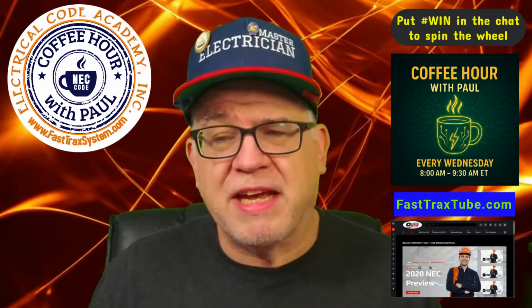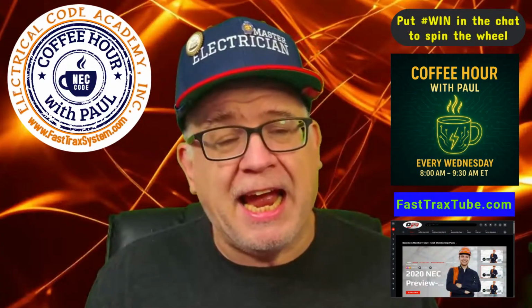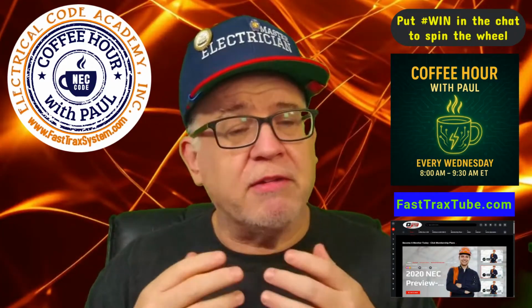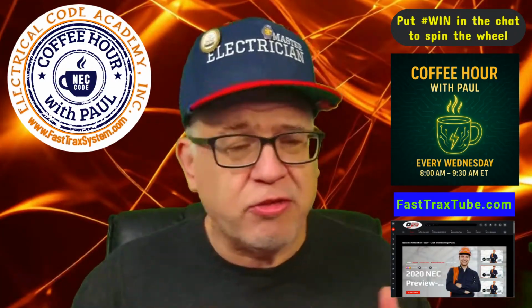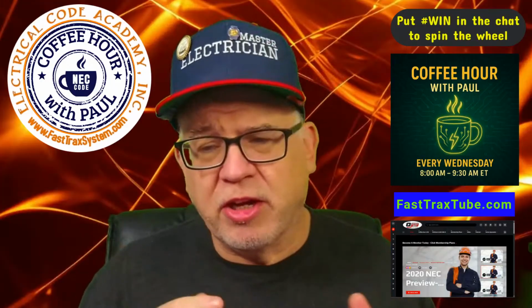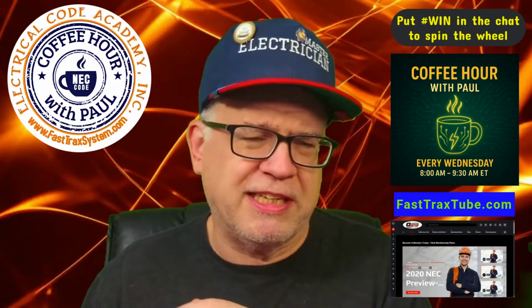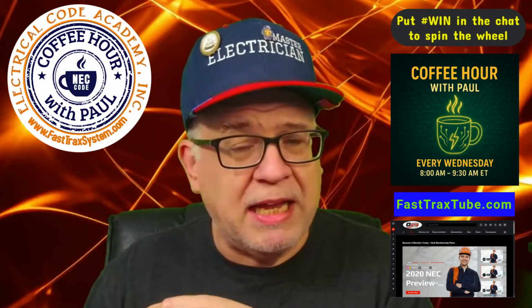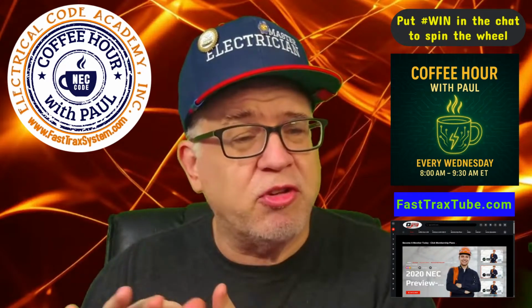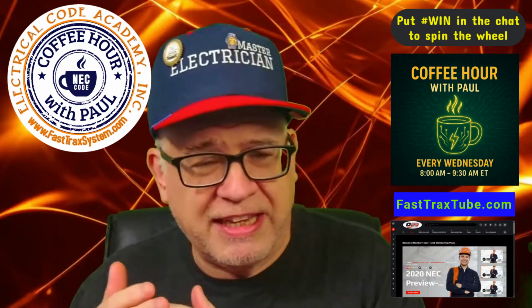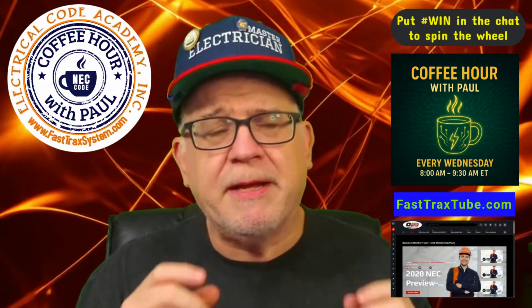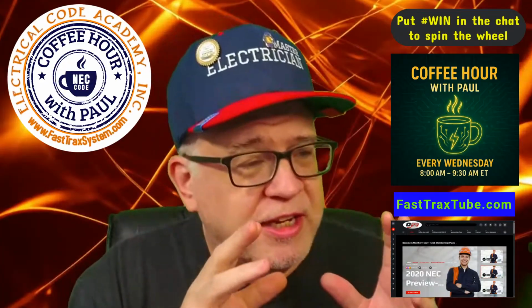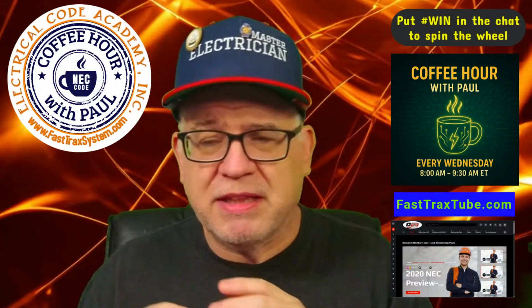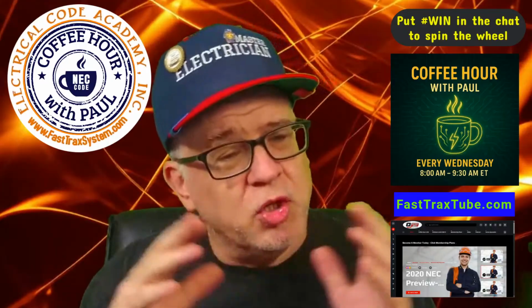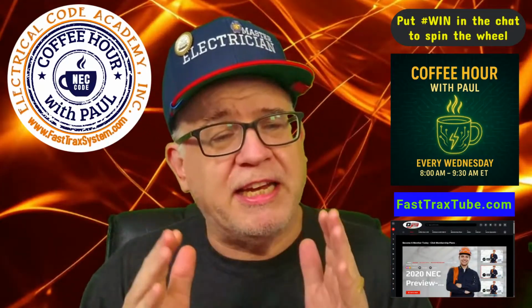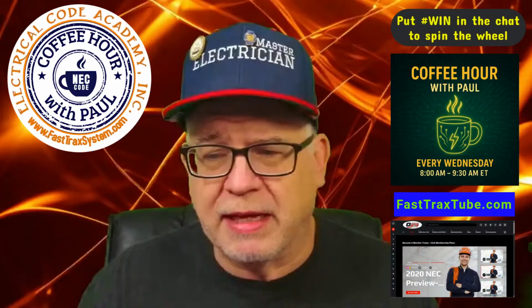270 is going to be breaking out the grounding and bonding, whereas 250 is traditional grounding and bonding, and you're going to have special applications for over 1,000 volts when it comes to grounding and bonding as well. So we've got 270 introducing that. Most of it's probably going to be cut and paste, but there's a significant move to differentiate and give you additional rules for grounding and bonding in 270.